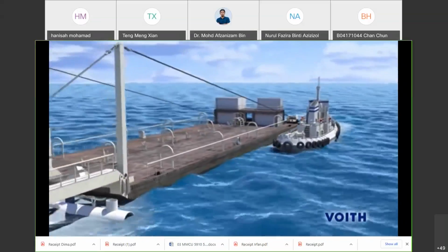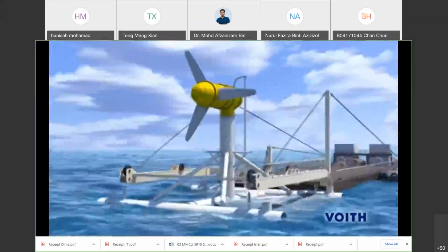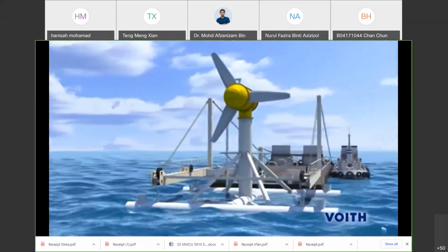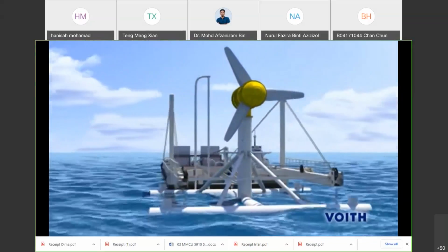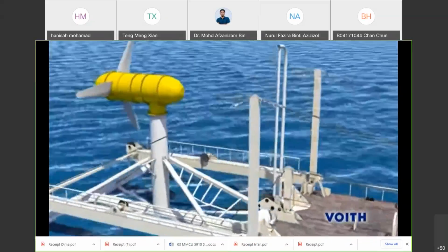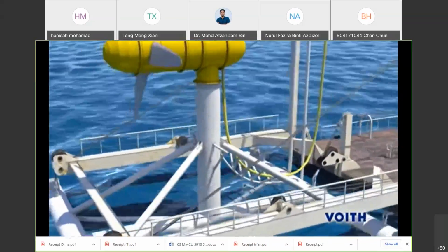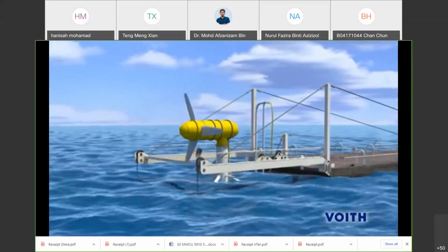The dimensions of a tidal current turbine are impressive. The turbine nacelle is almost 13 meters long, and the rotor has a diameter of 16 meters. In total, the plant is 26 meters high, which amounts to the size of a 7-story house. Once the installation vessel has reached the intended location for the underwater power station, the turbine is connected to a pre-placed subsea cable. For the future recovery of the turbine for maintenance purposes, guide chains are fixed to the foundation. The entire unit can now be immersed.